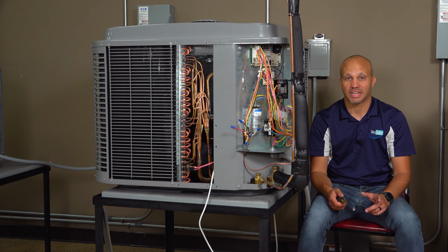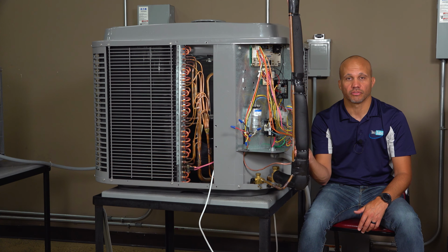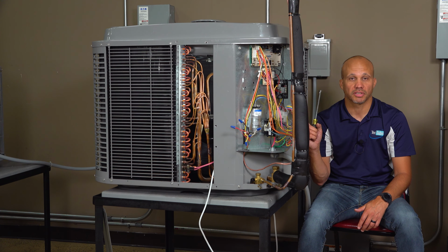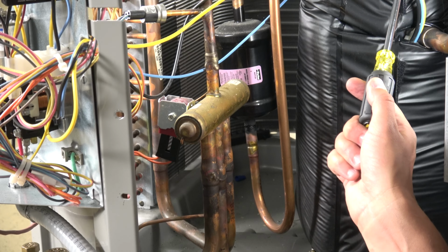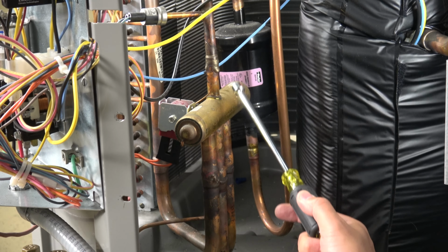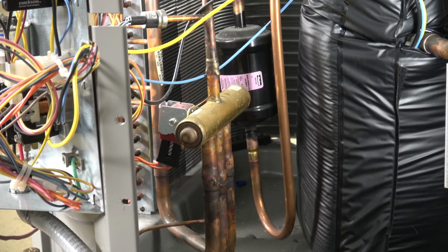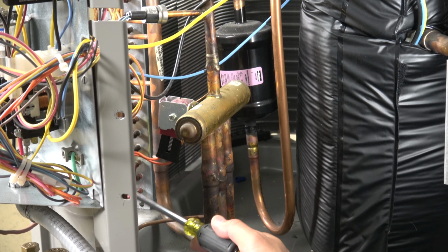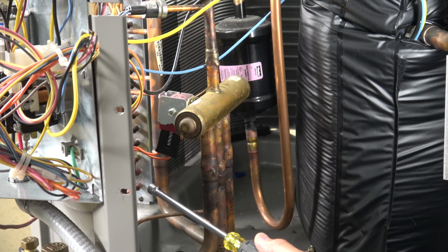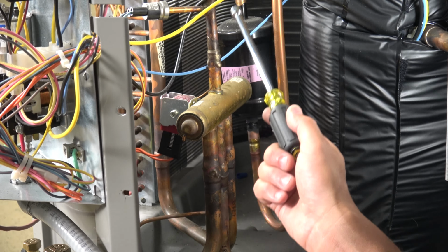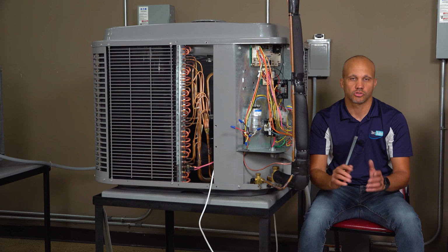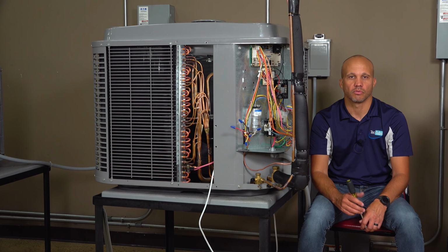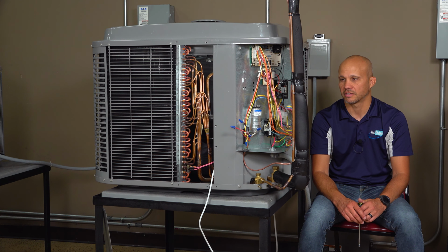When we ask the system to go into heating mode, the reversing valve slides over and flips, and now the outdoor coil becomes the evaporator coil and the indoor coil becomes the condenser coil. So now the hot gas coming off of the top of the compressor comes into the reversing valve and gets routed back out to the indoor unit, and it comes back in the other pipe from the indoor unit and goes to the outdoor coil, which is now the evaporator coil when we're in heating mode, on the other side of the reversing valve, and then back down into the compressor to restart that cycle again. Essentially those two coils just switch jobs, and the compressor doesn't know what's going on. It just makes higher pressure and that's it.